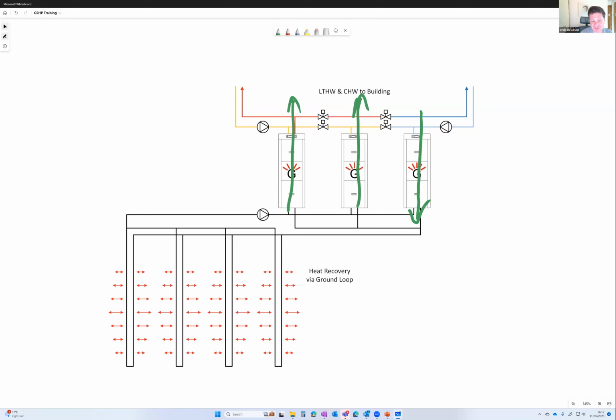However, the magic of ground source really is when you start to do that energy recovery interseasonally in the ground. We can do heating-only systems and cooling-only systems, but if we've got heating and cooling going on, things get very interesting in terms of interseasonal energy storage. I'm often asked what percentage you get back, and it could be anything north of 90–95% of that energy if the ground conditions are right. I'll show you an example of that at the end of this whiteboard session.